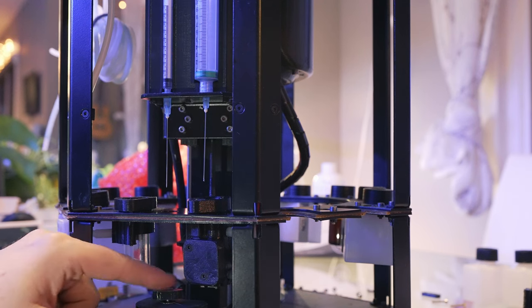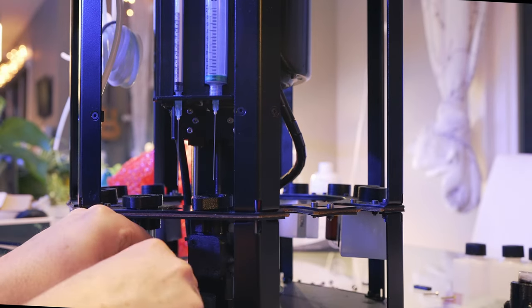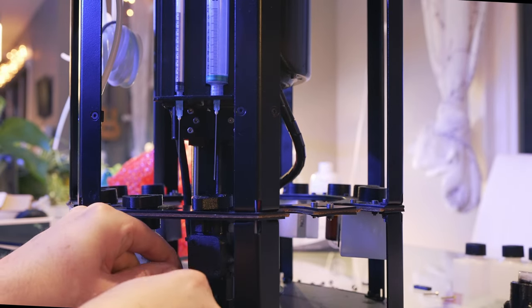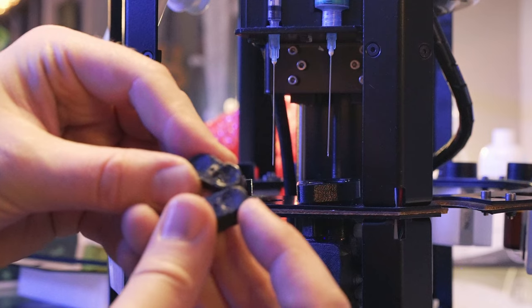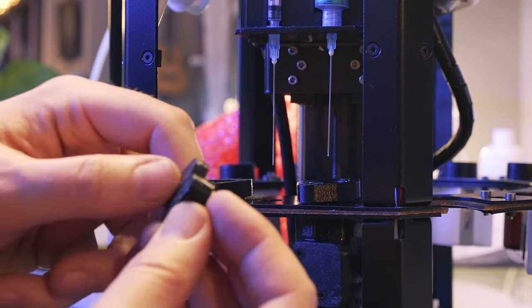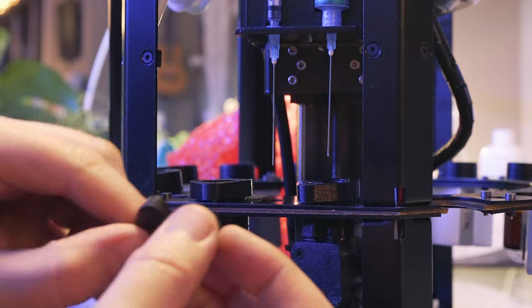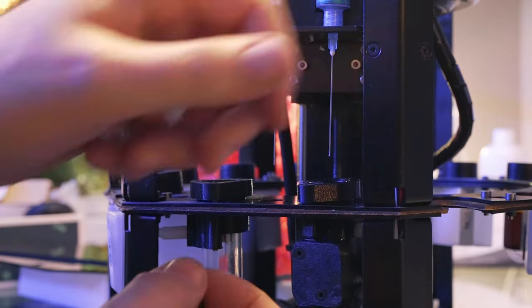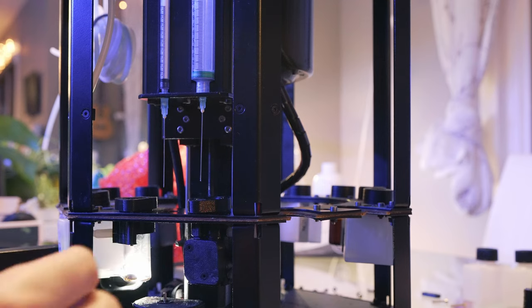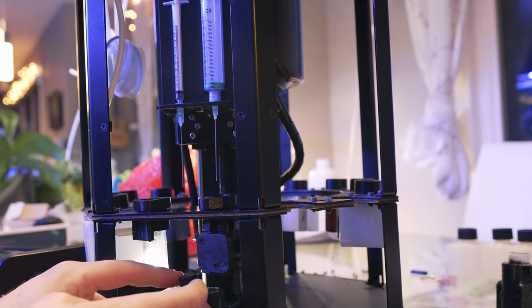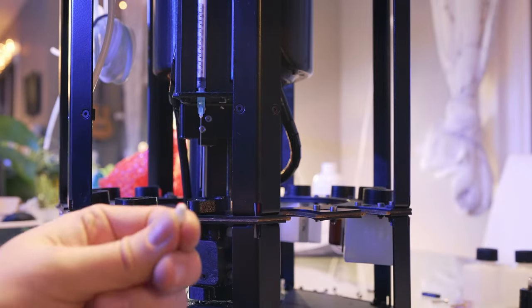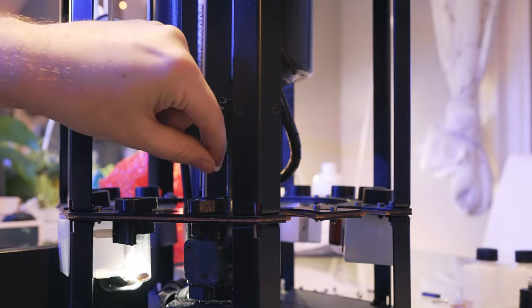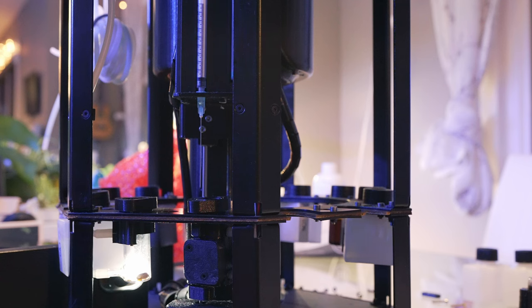The other next little bit we're going to do is replace this stir bar head. And I'll see if I can pop that off. It does look like there is bigger circles, so likely larger magnets inside. And if you look at the size of it, it is taller. So that would be putting the magnets closer to the vials, which probably increases the torque and capacity that it has. That was a super easy install. Do not forget to replace the tiny little pill inside the reaction chamber. Very important. Because you will not get proper test readings without that one.